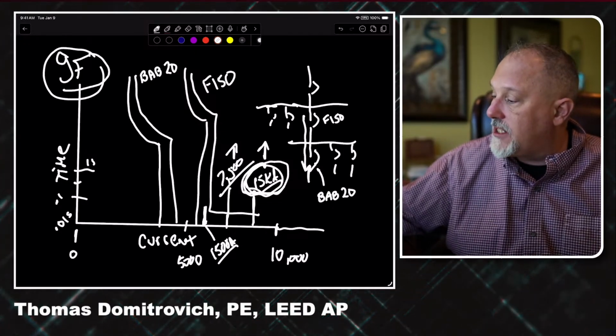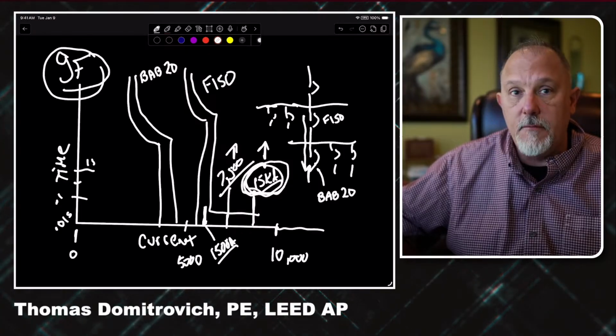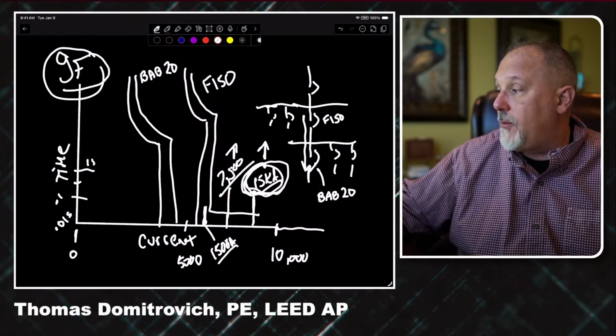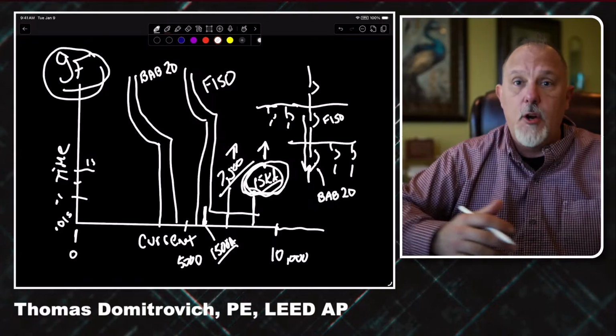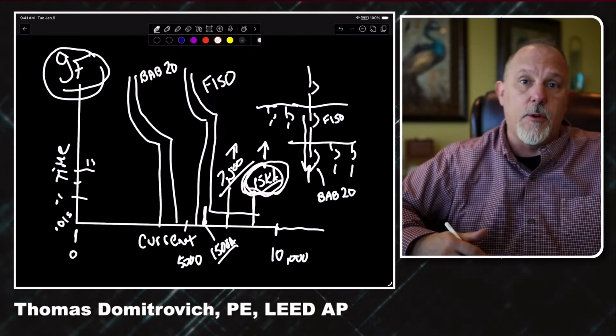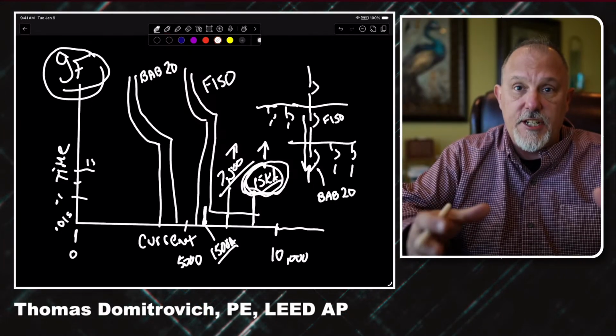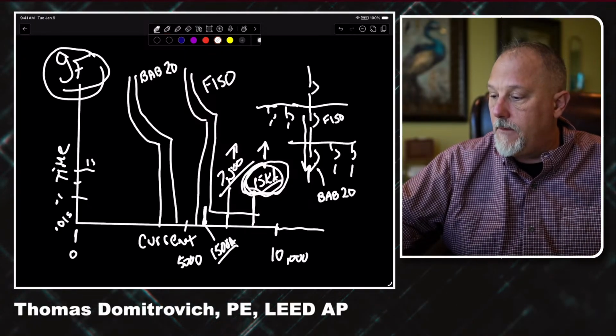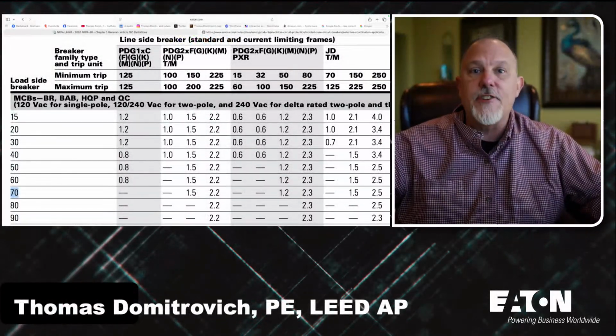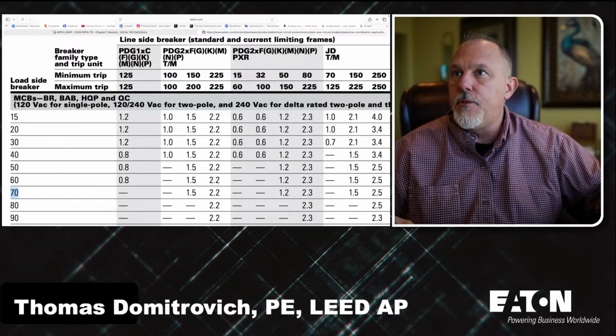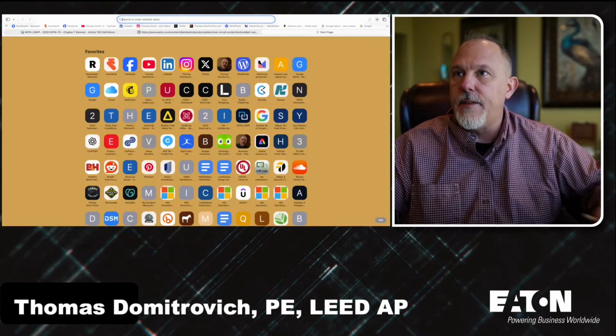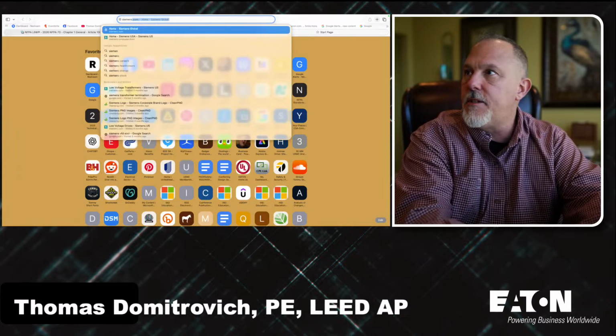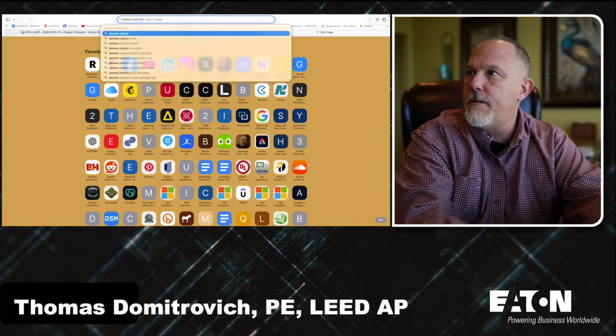When you get a current that's above the instantaneous of both, in the past, how did we fix it? We either lowered the fault current or we moved the upstream breaker to a larger breaker. The resource that you have today are the manufacturer's tables. So if I go to that, that's the Eaton.